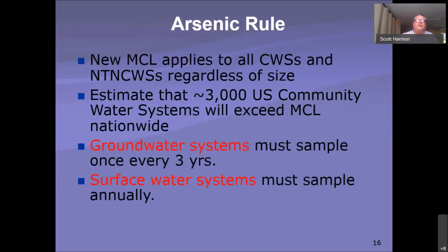This is essentially what they said. The new MCL applies to all community water systems and non-community water systems, regardless of size. They estimate that 3,000 water systems would exceed it nationwide. Groundwater systems must sample every 3 years. One of you folks said earlier that you don't treat for groundwater, but you test it every 3 years.